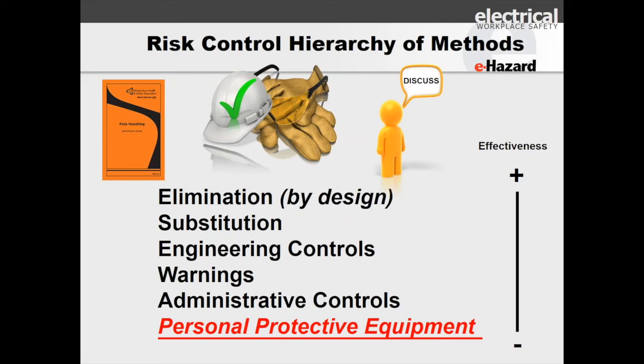The identification of hazards, shock, and arc flash numbers. You must have those risk assessment questions. Some of your people that have been in place for 15, 20 years, they know the value of the equipment. They know if it's good, if it's bad, if it's been maintained. All those things need to go into the equation for the risk assessment procedure, and we will get to the output of the risk assessment procedure very shortly. So that to me is kind of the way you get to pulling your personal protective equipment to do a real job, and it will get you in the ballpark of not overprotecting or underprotecting.